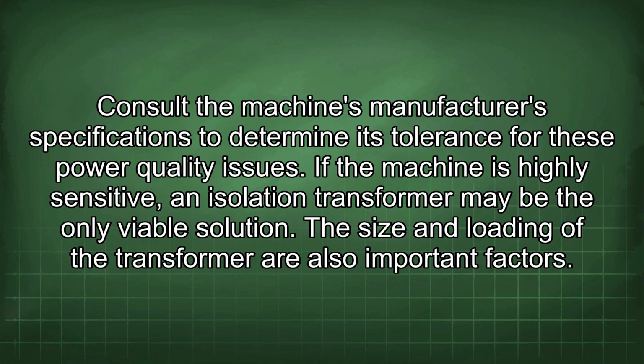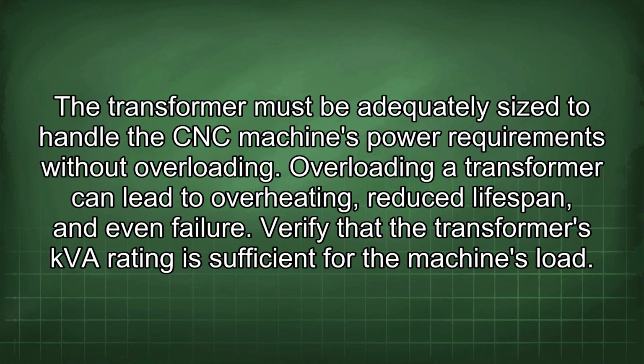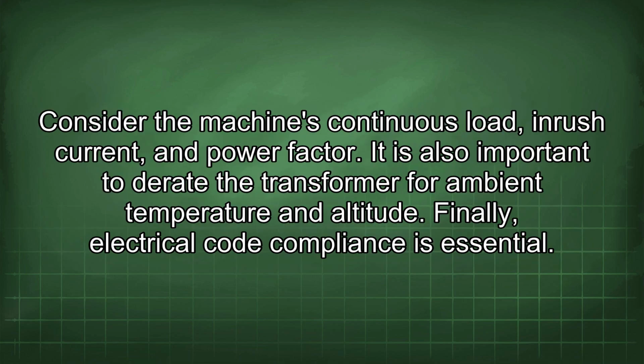The size and loading of the transformer are also important factors. The transformer must be adequately sized to handle the CNC machine's power requirements without overloading. Overloading a transformer can lead to overheating, reduced lifespan, and even failure. Verify that the transformer's kVA rating is sufficient for the machine's load. Consider the machine's continuous load, inrush current, and power factor. It is also important to derate the transformer for ambient temperature and altitude.